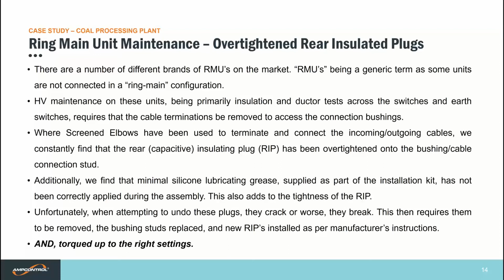High voltage maintenance on these units, being primarily insulation and ductor tests across the switches and earth switches, requires that the cable terminations be removed so that we can access the actual connection bushings and get our test equipment onto them. Where screened elbows have been used to terminate and connect the incoming and outgoing cables, we constantly find that the rear capacitive insulation plug, the RIP as we call it, has been over tightened onto the bushing cable connection stud. Additionally, we find that the minimal silicon lubricating grease that is supplied as part of the installation kit has not been correctly applied during the assembly. This also adds to the tightness of the RIP.